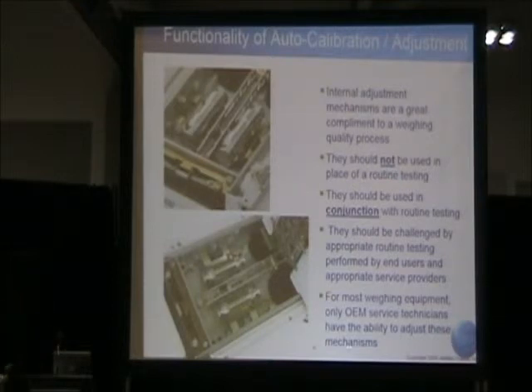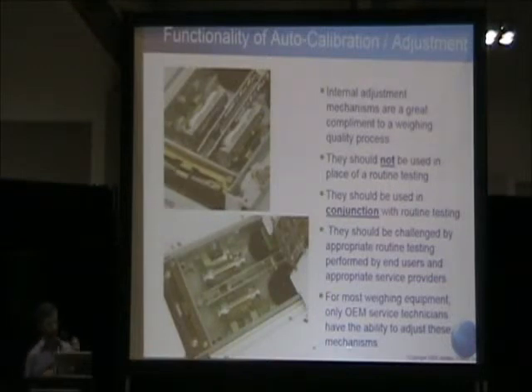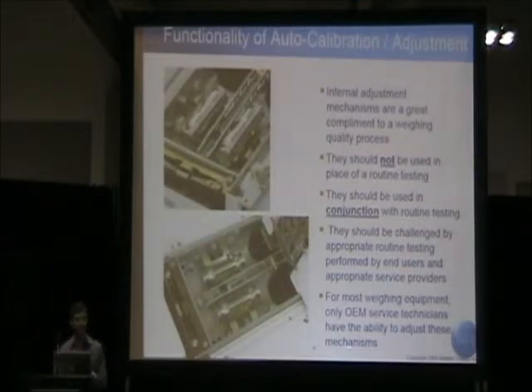The internal adjustments are great to ensure that throughout the lifespan of your instruments, in between calibrations, your uncertainty of measurement is at a bare minimum. But they should not be used only as a replacement of routine testing. They should be used in conjunction with it.